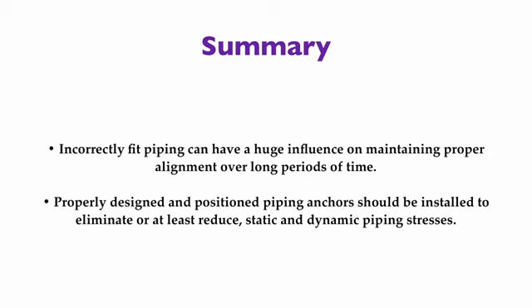Soft foot problems are far more prevalent than people realize, and the gaps that exist under our machinery feet are complex wedge-shaped gaps that cannot be fixed with flat pieces of shim stock. Soft foot is not discriminatory. It occurs on motors, turbines, pumps, fans, generators, gearboxes, and pillow block bearings. Again, anytime you attempt to mate one surface to another, there is a possibility of poor contact. It's not easy to fix, but it's very easy to ignore.